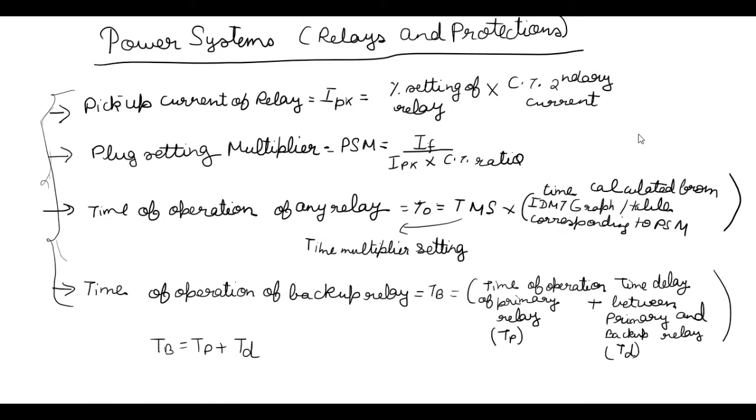So let's start with pickup current of relay, IPK, which is equal to percentage setting of relay into CT secondary current. So usually I think what is CT secondary current or what we have to do. Everything is there and I am going to answer everything in the question. And now the PSM, plug setting multiplier, which is IF upon IPK into CT ratio, where IF is fault current.